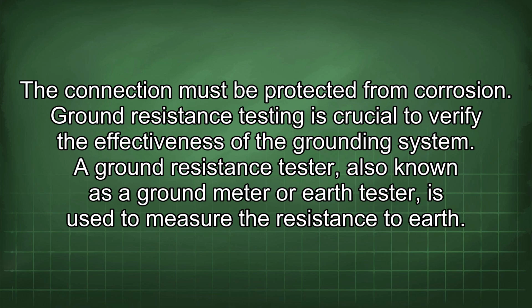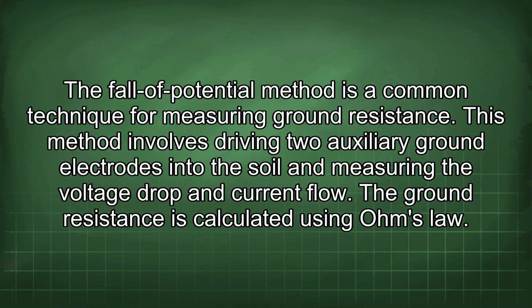Ground resistance testing is crucial to verify the effectiveness of the grounding system. A ground resistance tester, also known as a ground meter or earth tester, is used to measure the resistance to earth. Fall of potential method is a common technique for measuring ground resistance. This method involves driving 2 auxiliary ground electrodes into the soil and measuring the voltage drop and current flow. The ground resistance is calculated using Ohm's law.